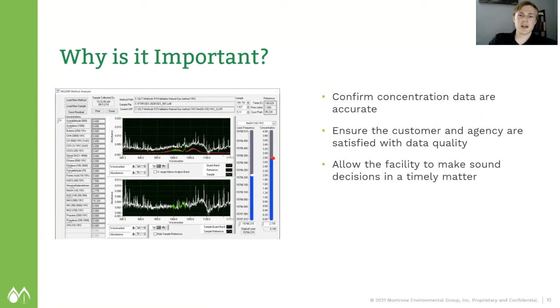And what this is essentially, you're confirming that the concentration data is accurate. So in this case, we are looking particularly at methanol. And long story short, the FTIR was saying that the methanol was non-detect. It believed it was below 0.5 ppm. And it turns out there was a large interferent in the way, right in that same absorption. We added it in, and it turns out that the methanol was more around 2.5, 3 ppm. So still below where the client needed to be, but it was apparent that the FTIR was not giving an accurate number on site. And if we did not validate and check this data set, we would have submitted the wrong numbers to not only the state, but to the client.